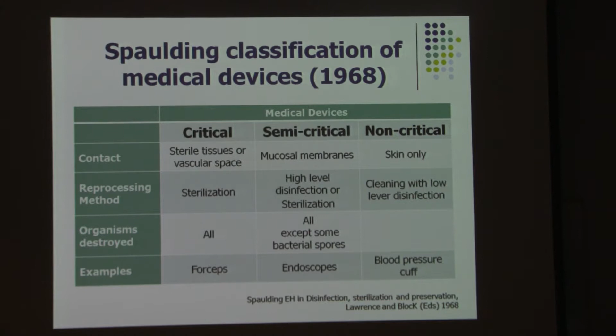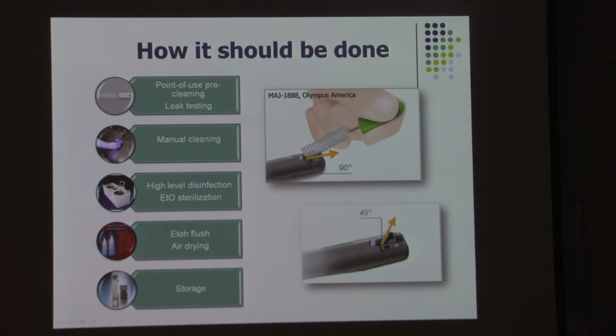So how should disinfection be done? High-level disinfection should be done. It starts in the endoscopy room with point-of-use pre-cleaning, and then moves towards leak testing, manual cleaning, high-level disinfection or gas sterilization, followed by alcohol flush and air drying, followed by storage. The reminder is that for Olympus equipment, we're required to use a special brush, and it is very critical to lift the elevator to at minimum 45 degrees and lift it and depress it several times during the process. There are multiple agents for high-level disinfection that are approved by the FDA. The one that's commonly used nowadays is peracetic acid.